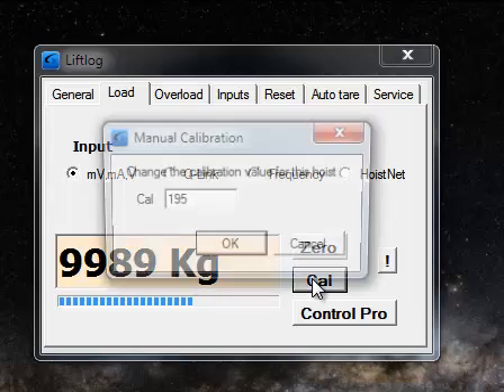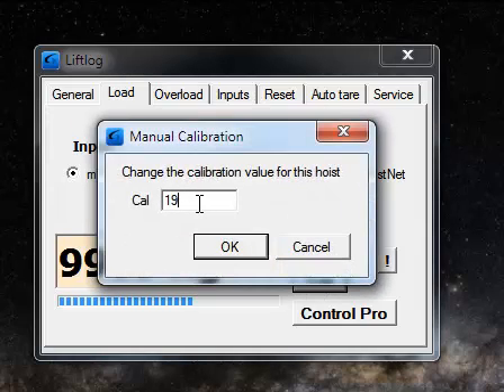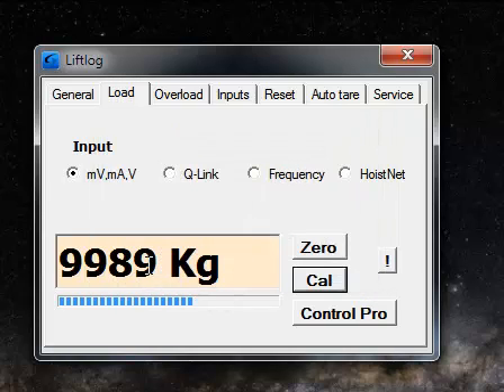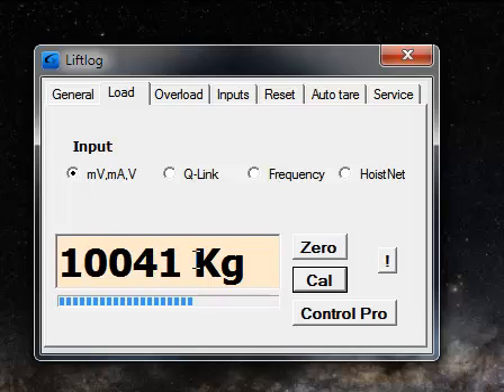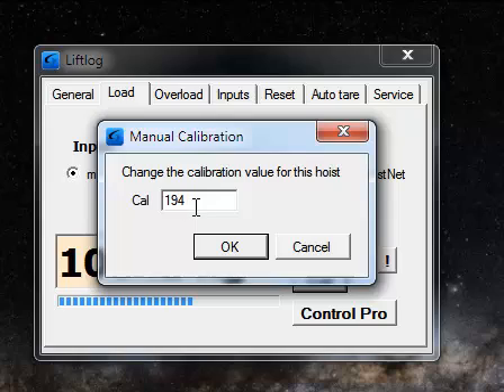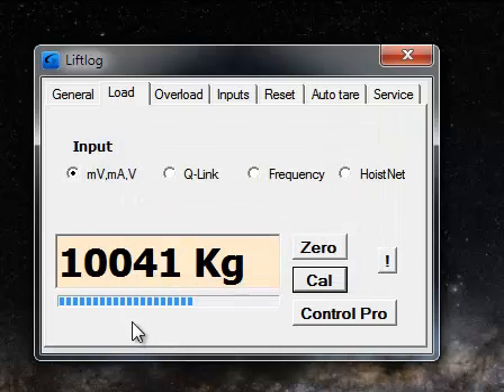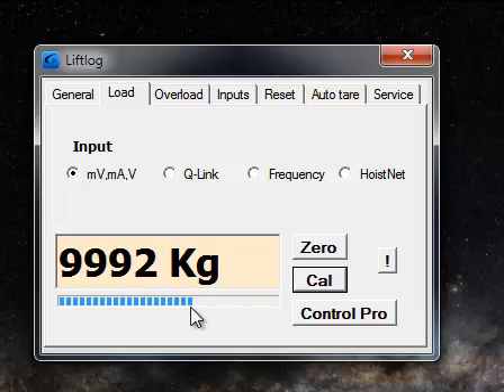And just to make sure there isn't anything better, if I change that to 194, so we're 10 kilos under here. With the 194, we go 40 kilos over, so 195 was the closest value we're going to get. Now, the smaller this number is, the bigger the change when you change one of these values. Again, I can't emphasize enough, it's important that you get a good size signal strength signal in when you go to do a calibration on your cell. If you don't, then you need to increase the gain.